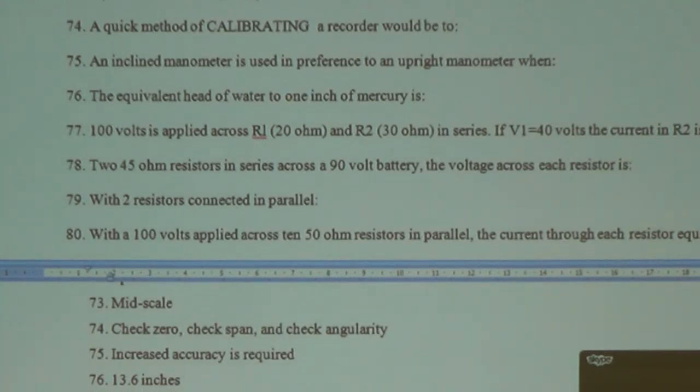In order to reduce angularity errors, the input and output lever must be parallel at mid-scale. Equivalent head of water to one inch of mercury is 13.6 inches of water, but you can leave it. This is not something which we are going to remember.